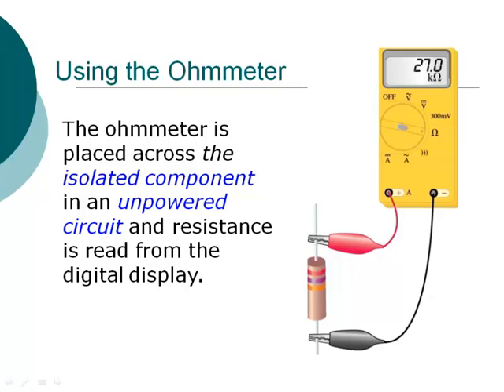We're going to use a multipurpose meter — you can see there's a sign for ohms, volts, and amps on it. The key thing about measuring the resistance of any device is that you must isolate the component in an unpowered circuit. If you put the leads across a live circuit that has current going through it with your meter set to resistance, you're going to burn out the meter.